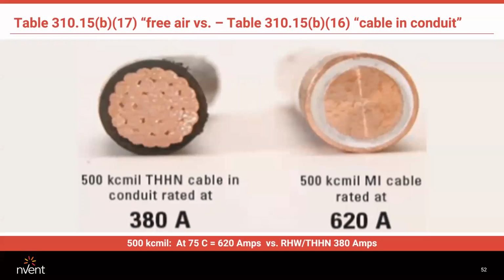There you go, right there. Our 500 kcmil, 620 amps, and THHN, 380. Now, this is very important, what I'm going to add here. The voltage drop for the MI cable is exactly the same as it is for pipe and wire for other cable systems. It's exactly the same. However, when you use our free air rating or any cable's free air rating, you will experience greater voltage drop for the simple reason that you're pushing more current through a cross-sectional area.